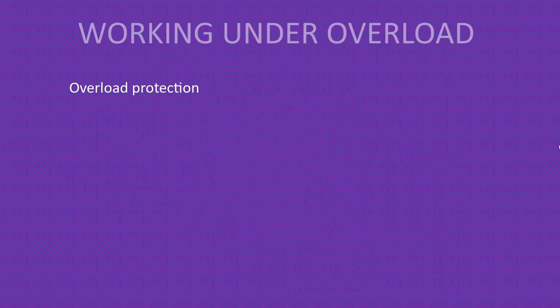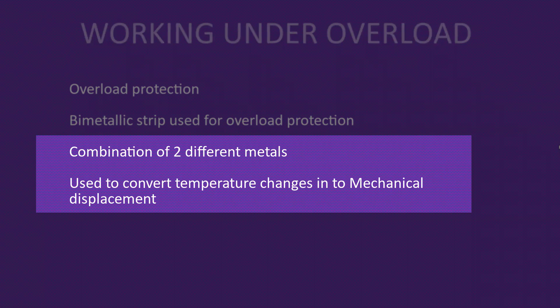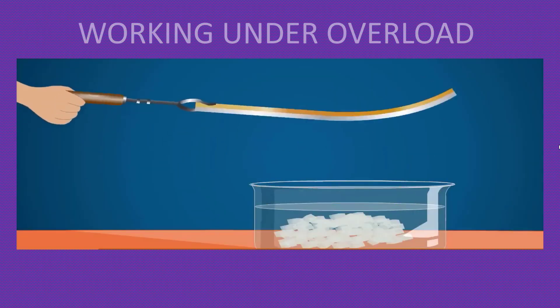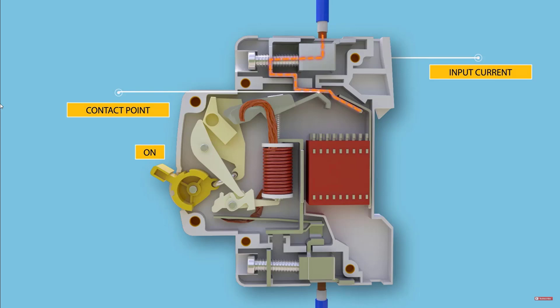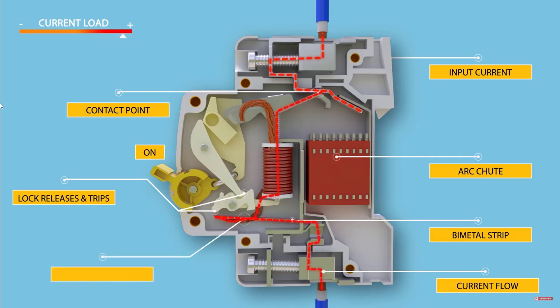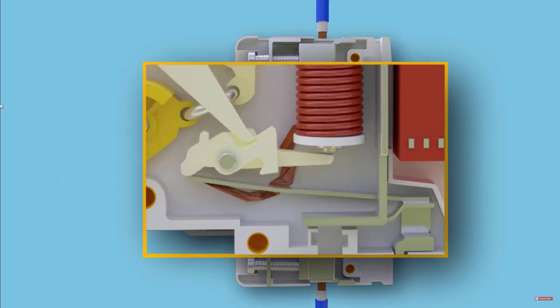MCB has two functions. The bimetallic strip is used for overload protection. A bimetallic strip is a combination of two different metals and is used to convert temperature changes into mechanical displacement — that is, if heated, the bimetallic strip bends, and if the temperature becomes normal, it returns to the same position. If the current passing through the MCB is more than the rated current, temperature starts to increase. This overload protection is a time-taking procedure. For small variations, the bimetallic strip won't activate suddenly. If the higher overload current continues to flow for some time, the bimetallic strip starts to bend, triggering the tripping mechanism — the fixed and moving contacts — and the circuit breaker will trip.